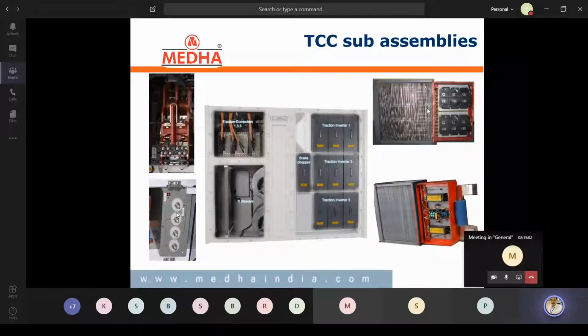So electrical and electronic devices are up to here only. This entire portion is mechanical for the cooling arrangement. This side up to this red area, this is electrical and electronics. So at the back side IGBTs were placed, and this side it's power supplies and gate drive modules, and for providing safety, each and every IGBT is placed with one PT100 probe. So here we can find this is the PT100 probe, temperature probe, to measure the IGBT heatsink temperature as a primary protection. And in case it is faulty, then a secondary protection thermal switch is there.